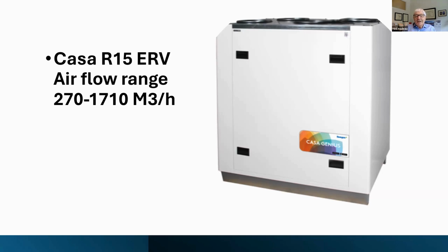But we're over-ventilating and that costs too much. I've heard that way too often. Well, who cares when your heating costs are $30 to $50 a year? The multiple effects of a 90% reduced heating load, the 85% efficient ERV, and the heat pump COP of 3 reduce the penalty for over-ventilating to a cup of coffee.